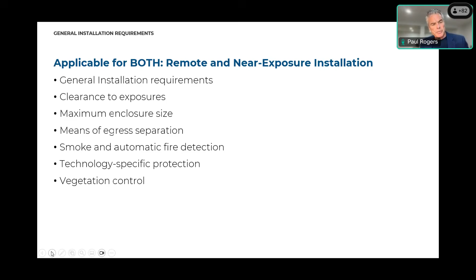And the clearance to exposures, I think we said the minimum is 10 feet from the lot line, public ways, and buildings and so on. We want to make sure there is a 1-hour fire barrier 5 feet above, which really gets into the residential part of it. But the minimum is 10 feet. Can you go further? Yeah, but again, using the UL 9540A testing results will help you say, yeah, we went further based on heat flux or whatever it may be. So we can go on to the next slide.